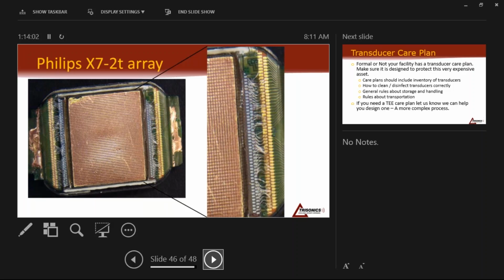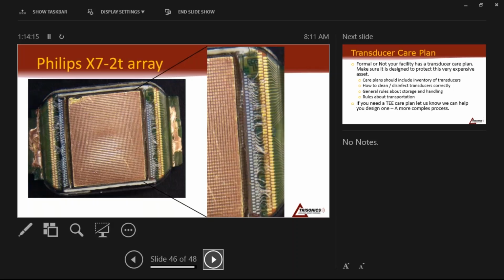This particular one has been out, and it's gotten mangled by people touching it. It's a terrible case of it. All of them are smashed together. But all it takes is one drop of water to drop on there, and we always say that the ASIC blows. We don't really think it is the ASIC. It's just the wiring, and there's no coming back from that. We can't fix that. That's why it shouldn't be touched up. So any little bit of water kills it. This would be the same on the Philips X7-2, X8, probably the GE V6, whatever the rest of it is, can't think of it at the moment. That's why. And it's pretty small. This whole thing is smaller than a dime.